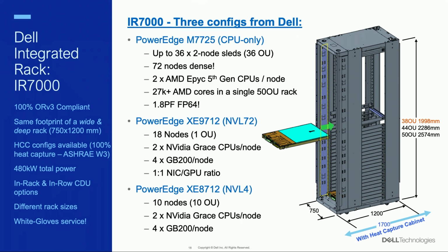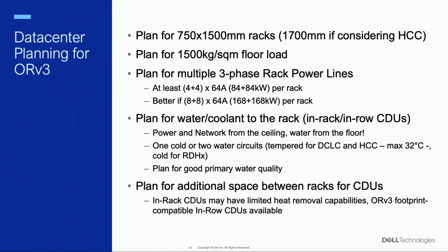As a last point, my two pennies if you want to do data center planning for this new generation: planning is key. You have to plan for floor space. If you're looking for a liquid cooling solution, you might need to consider CDUs if you're deploying more than three racks, because those racks can host an internal CDU, but we've seen that the break-even point between an in-rack CDU and an in-row CDU is around three racks.